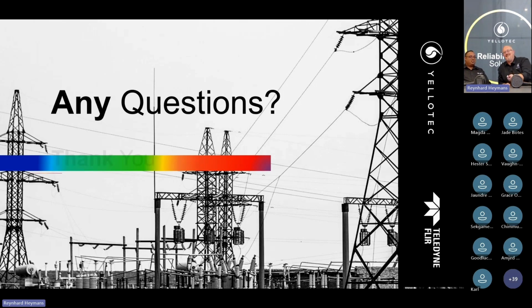Got a new question, let's go back to it. Is it possible to pinpoint faults on a MV-MCC panel? MV-MCC, medium voltage motor control center. Yes, you can, so long as, well, it becomes a question of whether it's line of sight, whether you're able to see it. But remember, if there's any partial discharge within the panel, using the device you'll still be able to detect it, as the sound will escape from some point or other. So you do have some reference point to say this particular panel has some sort of discharge.